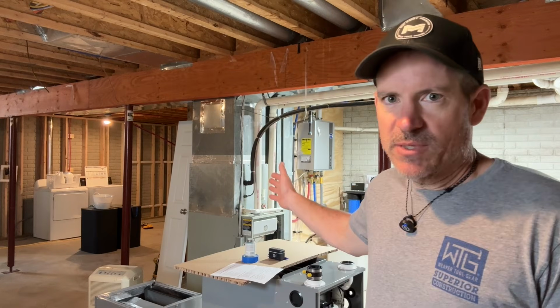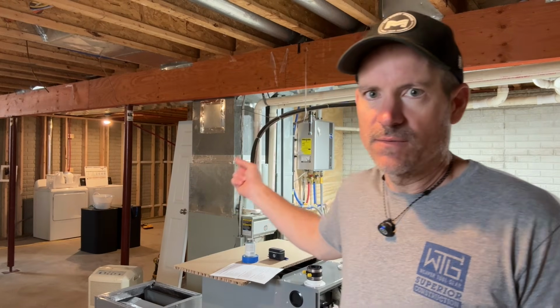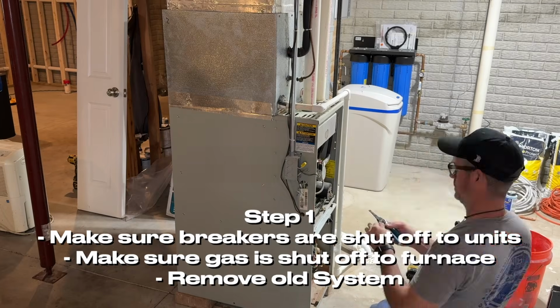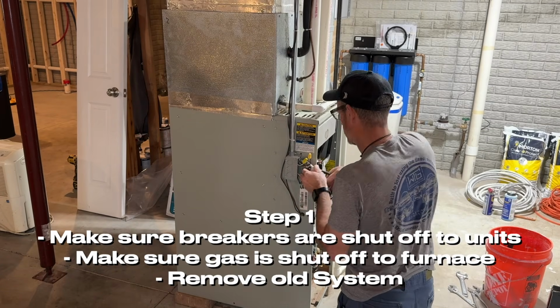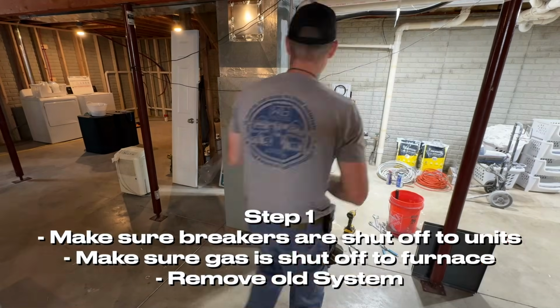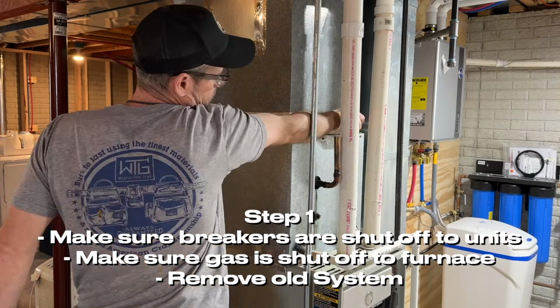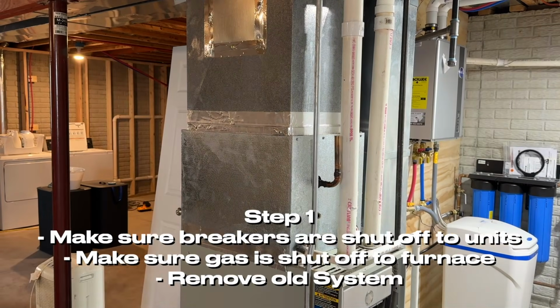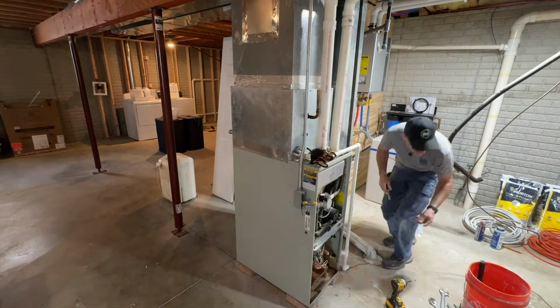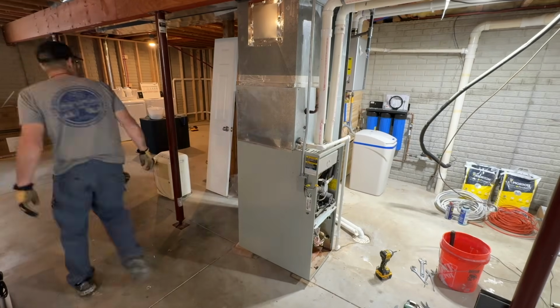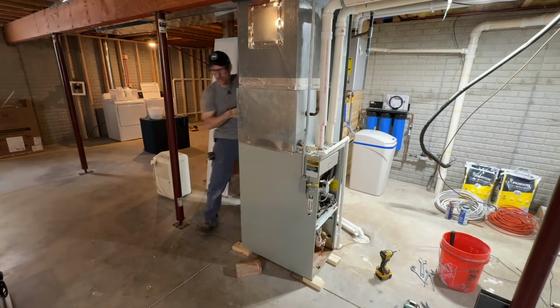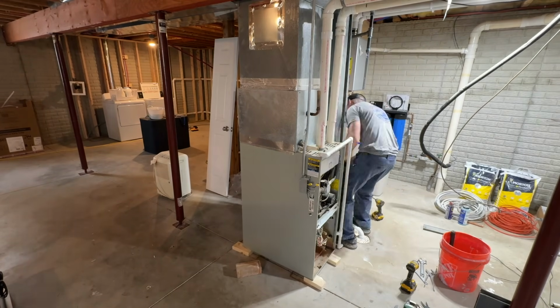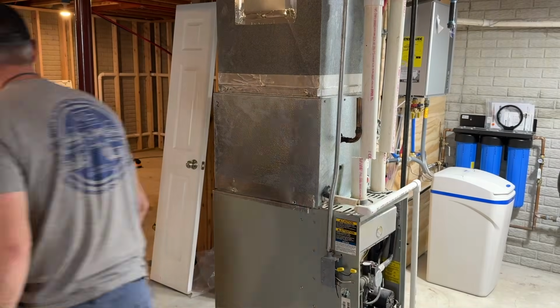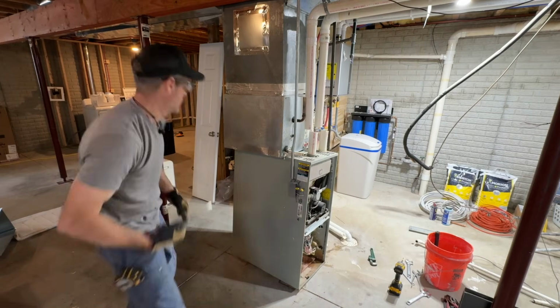All right, guys, this might be the most important part of finishing off this whole house remodel and finishing the basement. Step one is to remove the old unit. Make sure that the power is turned off to both units, both the furnace and the condenser outside. Then make sure the gas is shut off to the furnace, and then you can remove the unit safely without any issues. I hired an HVAC company to come and remove all the refrigerant.